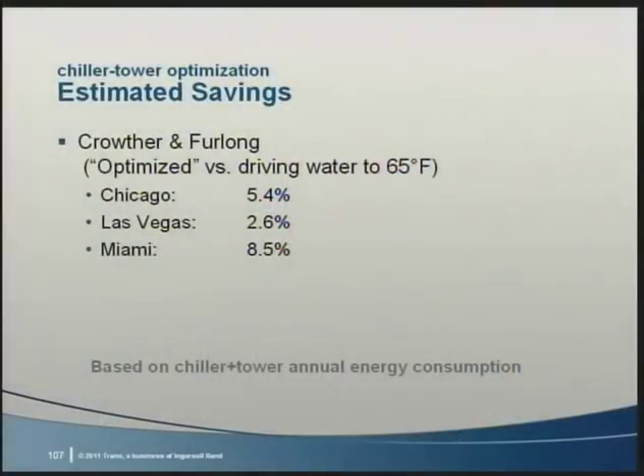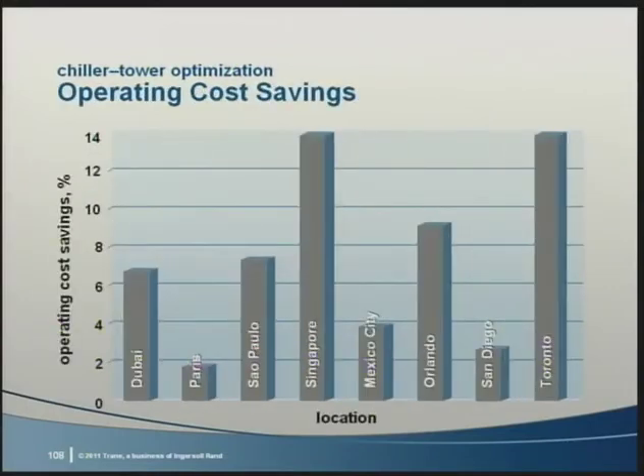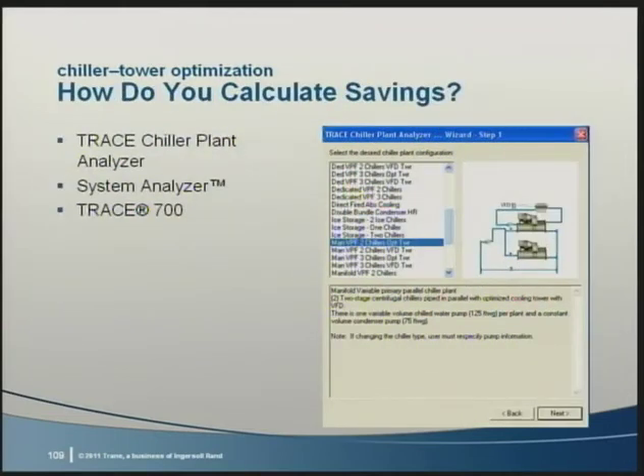In their ASHRAE Journal article, Hugh Crowther and Jim Furlong estimated savings from 2.6 to almost 8.5% by finding the optimal tower temperature. And in our E&L on cooling towers, we showed savings up to 14%, depending on location, in this case for a hotel. Specific project estimates of savings can be made in half an hour by using software such as Chiller Plant Analyzer. Okay, let's go further now.